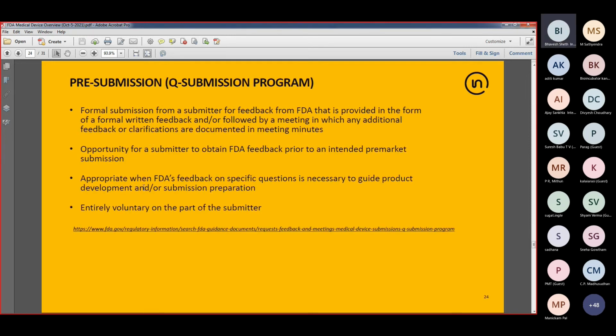So when discussing De Novo, I had mentioned pre-submission. This is another type of inquiry process, which is also called the Q-Submission program. So you can use this pre-submission approach before submitting a 510K, before submitting a De Novo, before submitting a pre-market approval. The benefit is that you can actually share information with FDA about the type of testing you are planning to do and ask FDA very specific questions, whether that testing is adequate, whether you are missing anything, just to get more confidence for your regulatory submission. The downside is that FDA takes over 2 months to review the pre-submission.